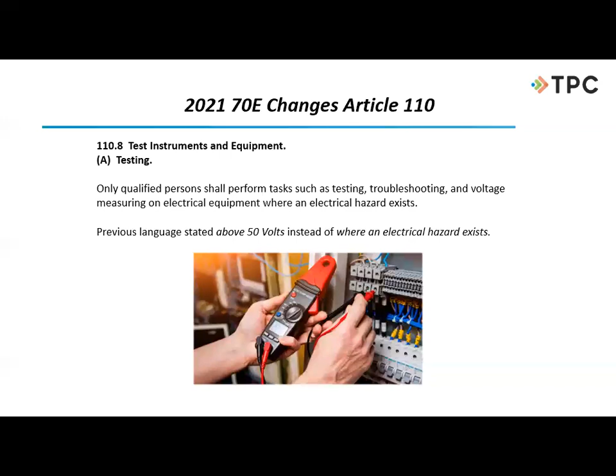This in 110.8 is also a change for us. It used to say that when using some type of test equipment, it applied above 50 volts. Now it says, at the end of the sentence, 'where an electrical hazard exists.' So we have to be qualified to use a piece of test instrument wherever there's an electrical hazard. That means not just a shock hazard -- above 50 volts would indicate only shock -- but if we're at 1.2 calories per centimeter squared or above, there's an arc flash hazard too. They wanted to make sure it covers any electrical hazard, not just shock.